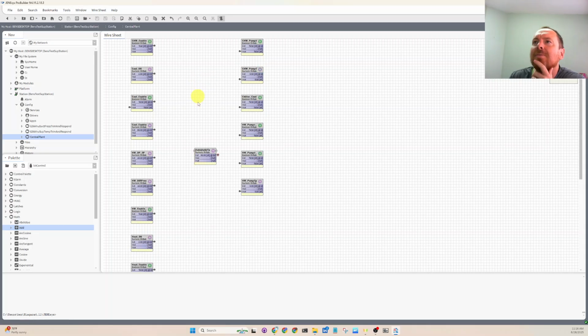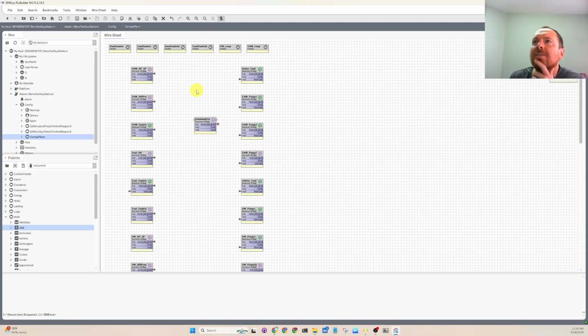Let's drag around our outside air temp. Okay, so this is our outside air temp. In the field, we would be linking this up to the actual sensor for the building. Okay, 60 degrees F, that's in degrees Fahrenheit. That's kind of on the high side of the economizing end, so we shouldn't really need a chiller, and we shouldn't really need a boiler. So let's see, our logic should be running.